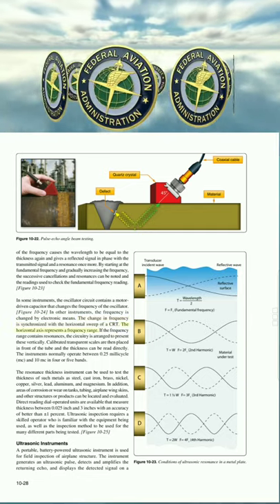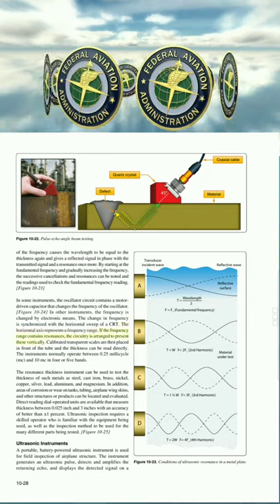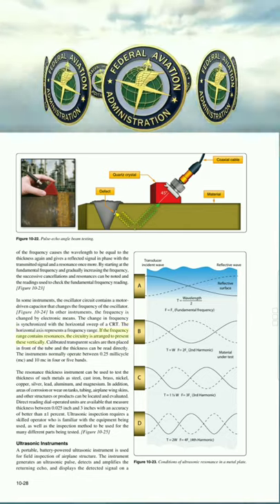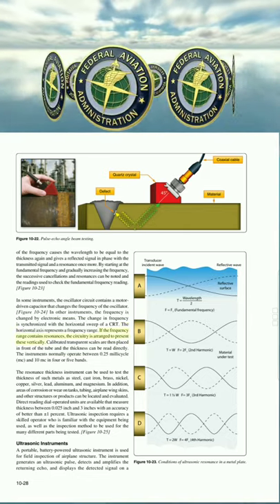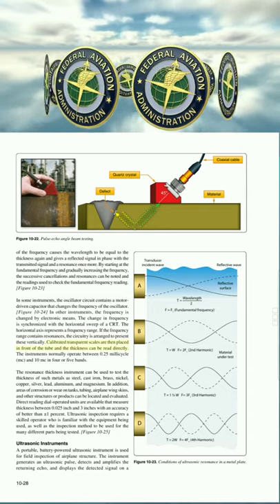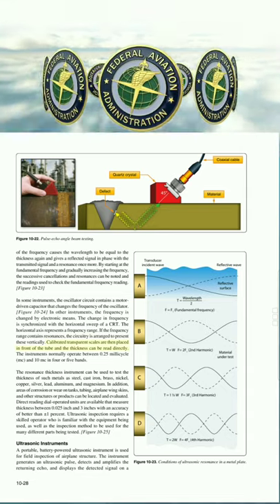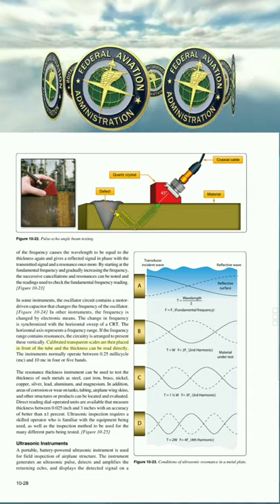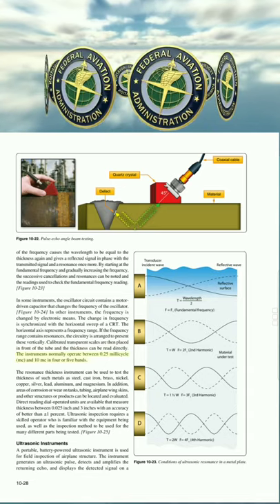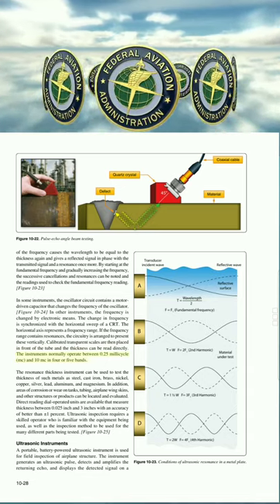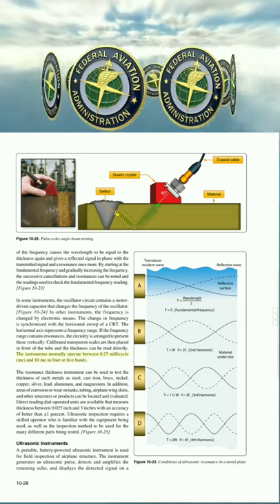The horizontal axis represents a frequency range. If the frequency range contains resonances, the circuitry is arranged to present these vertically. Calibrated transparent scales are then placed in front of the tube and the thickness can be read directly. The instruments normally operate between 0.25 millicycle (mc) and 10 mc in 4 or 5 bands.